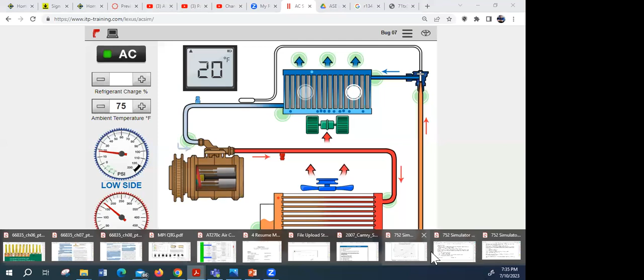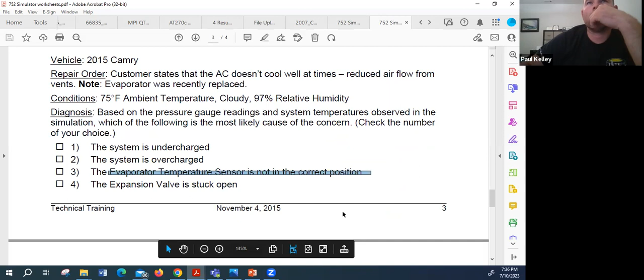The sensor, the evaporator temp sensor. Look at that, 58 degrees. What's the actual temperature? 20. And that's not even close. So if our temperature sensor is laying in the bottom of the box, that would cause the compressor to continue doing maximum stroke, which would actually draw the low too low. Once you get down to 20, the air that hits this with moisture, that humidity, is going to freeze to it. You guys can see how the answer would be, what do you think, the position of the sensor. Yeah, the sensor's laying in the bottom of the box. There you go, boom, there you go.